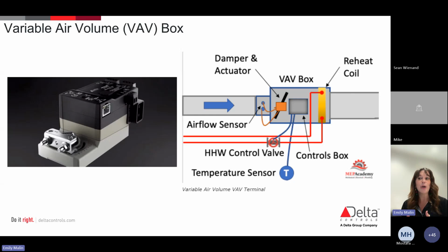Next, we're going to see a damper. A damper is what's actually going to control how much air is being let through. An airflow sensor is what's going to monitor that rate of airflow. And then an actuator is what's actually going to move that damper. Actuators in general are the pieces that work by receiving a control signal. So when we talk about our controller, that controller is going to send a signal to the actuator. And that actuator is then going to use an energy source to create that mechanical motion of our damper. And we'll see how that works.